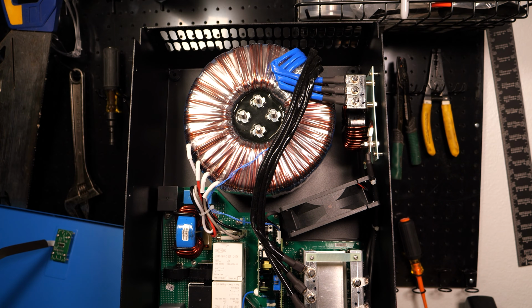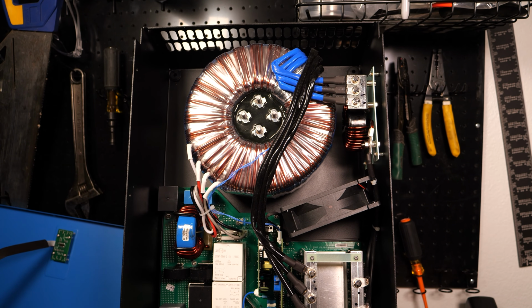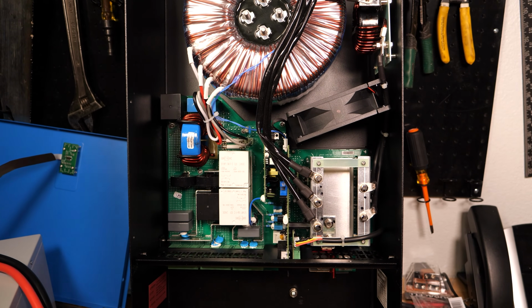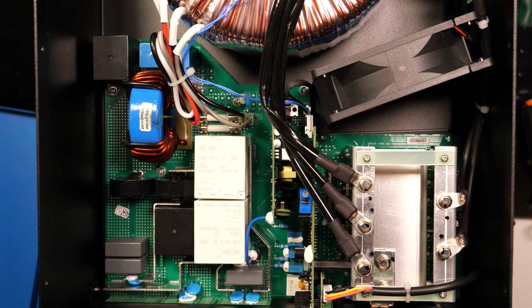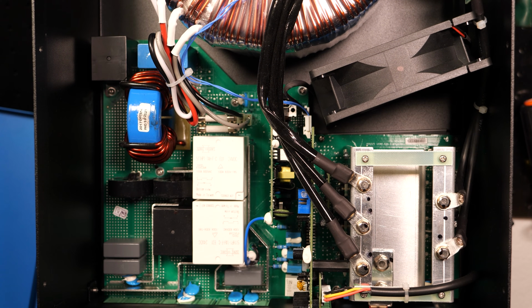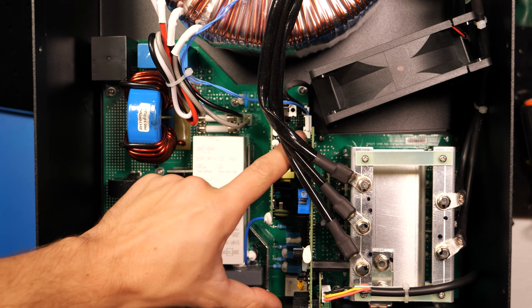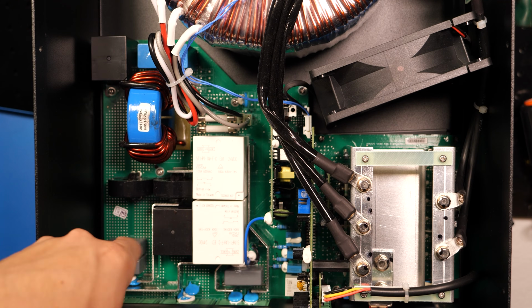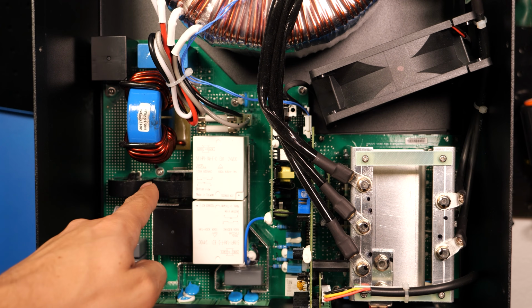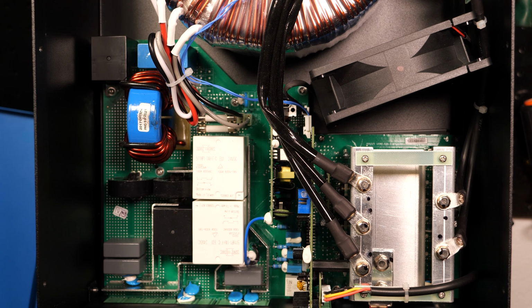That's because this is a low frequency inverter, and we're going to do some tests here in a minute to see if low frequency still means inefficient. It's blown me away over time how Victron has simplified the insides of their inverters. If I pan down here to the bottom and get into the control boards, there's not a whole lot to them. They have a simple compute board here that sticks up from the main board, and a power board down here at the bottom that just has some contactors, some current sensors, a big old inductor, and the H-bridge circuit. Aside from a fan and the transformer, there's not a whole lot in these, and I like that because that usually means there's not a whole lot to go wrong. They've really simplified and consolidated it down here on this one.